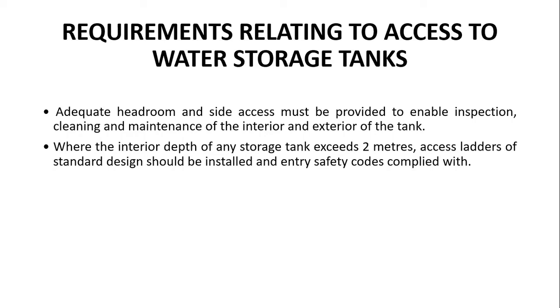Headroom is an extra space between a normal person's height and the top slab of the water tank. The depth of the water tank should not be less than 6 to 6.5 feet, so that a person standing inside the tank for inspection or maintenance can stand comfortably without their head touching the top slab. Wherever the depth of the tank exceeds 2 meters, a ladder must be provided. These ladders are designed to standard measurements so a person can reach the bottom of the tank, and they must comply with entry safety codes.